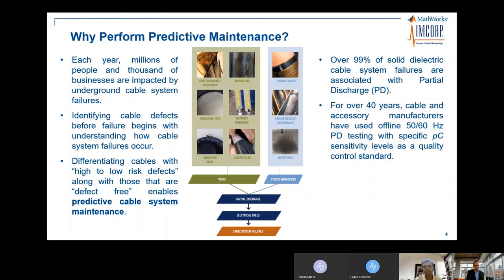Over 99% of solid dielectric cable system failures are associated with the effect called partial discharge. Partial discharge is a slow degeneration of the cable insulating material which eventually leads to failure. Over 40 years, cable and accessory manufacturers have used offline 50 or 60 Hz PD testing with specific sensitivity levels as a quality control standard.